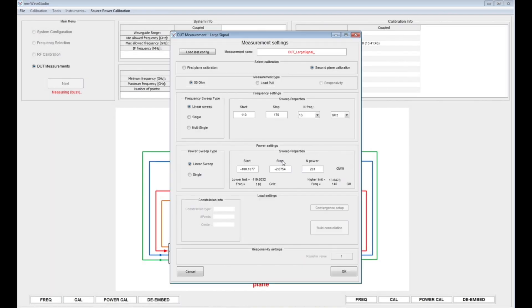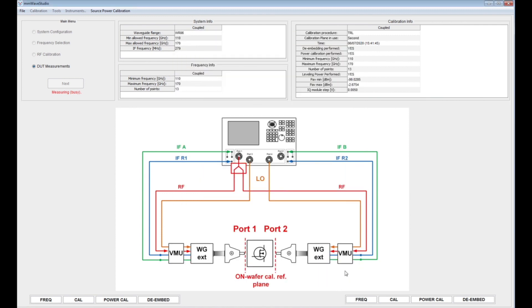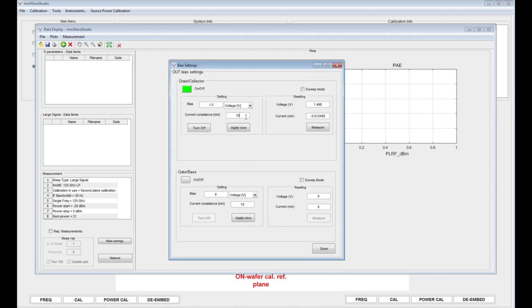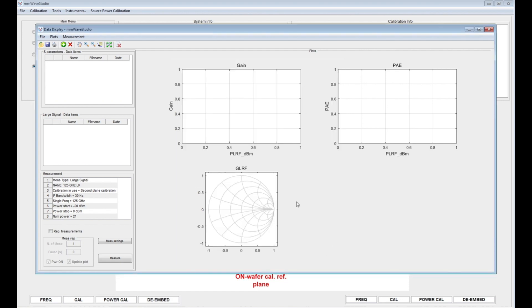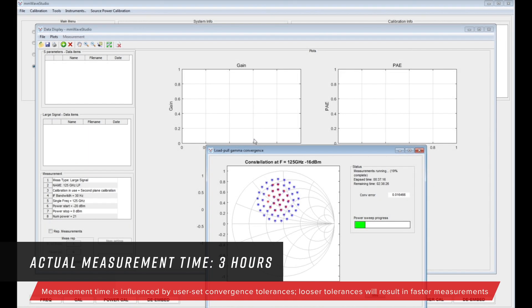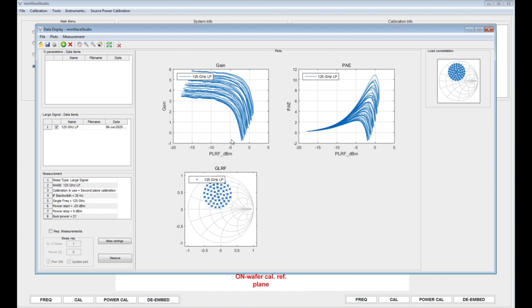Now we need to configure our load pull measurement. Once that is done, we can click OK and we are taken to the data display window. Before we can perform the load pull measurement, we need to bias our device. And once the device is biased correctly, we can start the load pull measurement by clicking on the measure button. When the measurement is finished, the results are shown in the data display window.